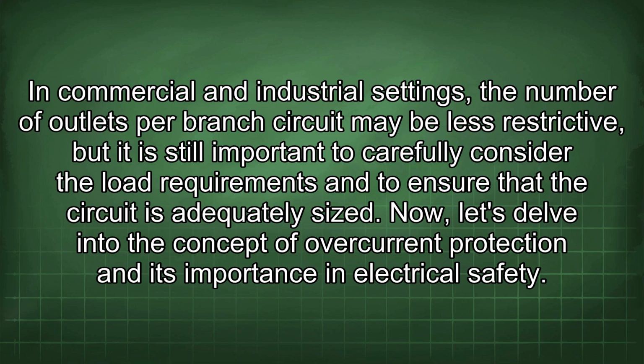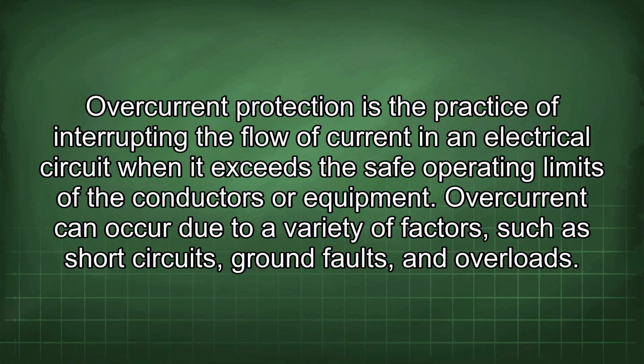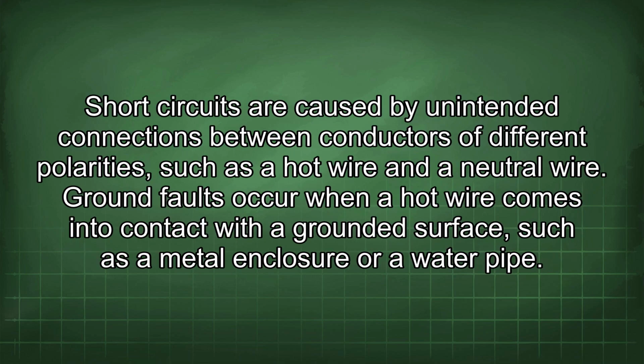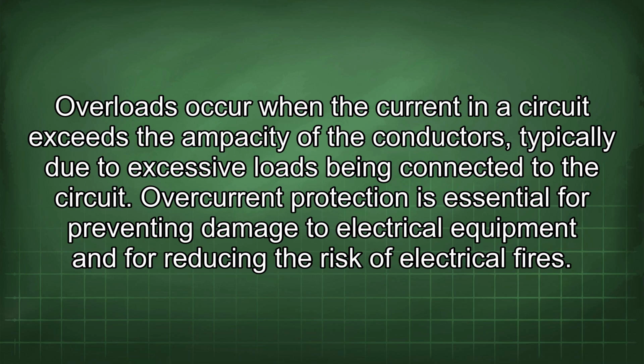Now, let's delve into the concept of overcurrent protection and its importance in electrical safety. Overcurrent protection is the practice of interrupting the flow of current in an electrical circuit when it exceeds the safe operating limits of the conductors or equipment. Overcurrent can occur due to a variety of factors, such as short circuits, ground faults, and overloads. Short circuits are caused by unintended connections between conductors of different polarities, such as a hot wire and a neutral wire. Ground faults occur when a hot wire comes into contact with a grounded surface, such as a metal enclosure or a water pipe. Overloads occur when the current in a circuit exceeds the ampacity of the conductors, typically due to excessive loads being connected to the circuit.